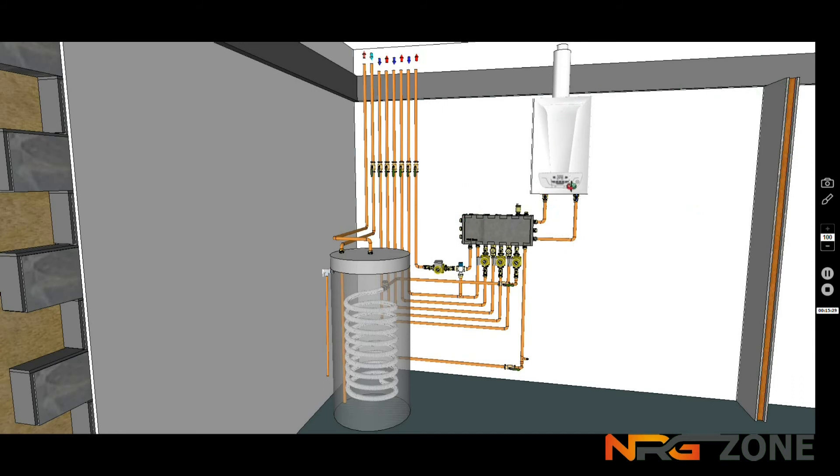I've shown here a boiler on the right hand side but just suppose we want to put a boiler on the left hand side, quite simple. Just use the top connection for the flow, bottom connection on the left hand side for the return. But just suppose you want to use two boilers, again not a problem because you can now parallel the two boilers. You could if you wish set one boiler at 70 degrees and the other one at 75 degrees. Both of them would come on and come up to 70 degrees. When one reaches 70 it turns off and the other one will keep the system hot. Of course that would be dependent on the type of boiler or how you're going to go about your control mechanisms. You could have a boiler on the left or on the right or two boilers. In fact other videos will show that you can actually even put more boilers onto this unit if you wish.